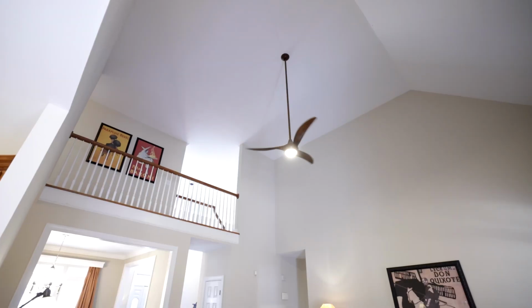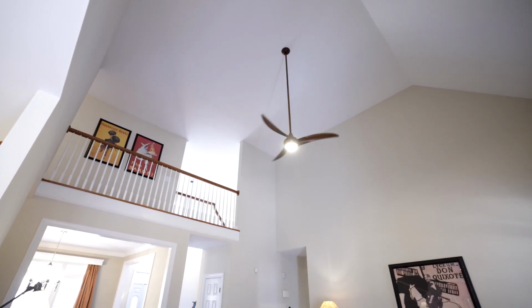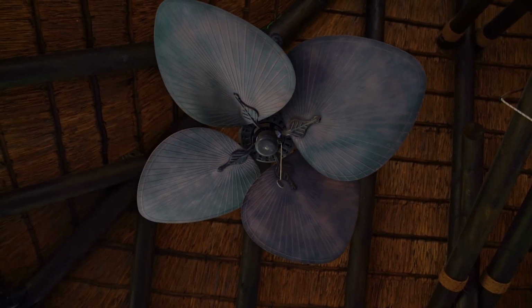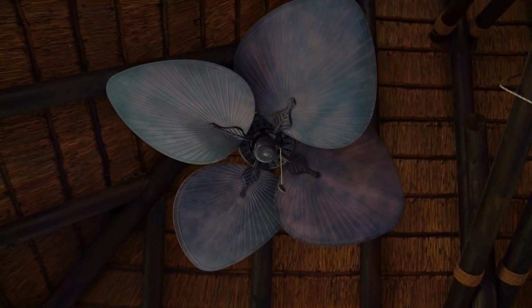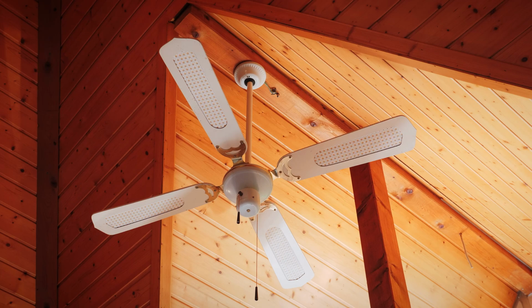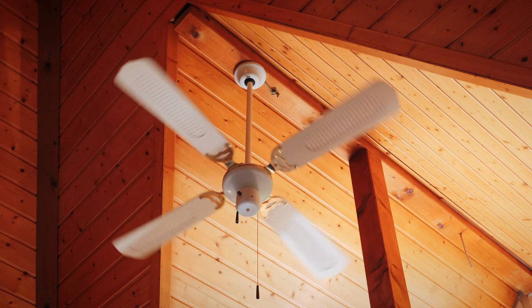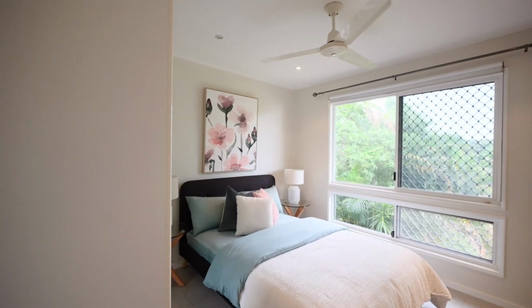The Fan Control Tree is the solution when it comes to integrating fans, such as ceiling fans, into a building automation system. It is optimized to connect to 60 watt fans, but supports fans from 30 watt up to 120 watt. It allows you to control the fan speed in four specific steps: low, medium, high, and maximum, and off, of course. This means in all scenarios where usually you have to have manual control, like manually switch it on and off or select the speed, you can now integrate the fan into your automation, which makes it perfect for both residential and commercial projects.